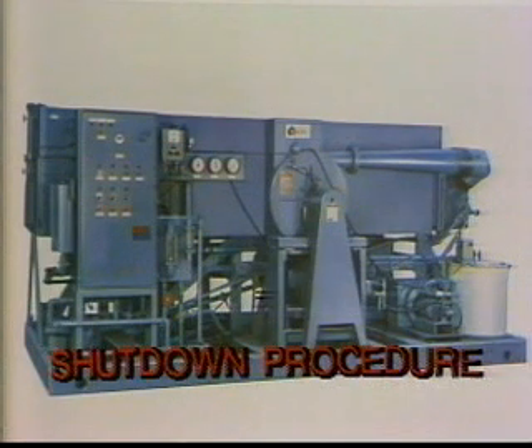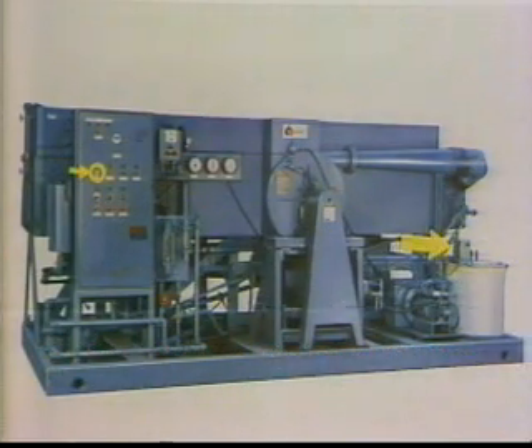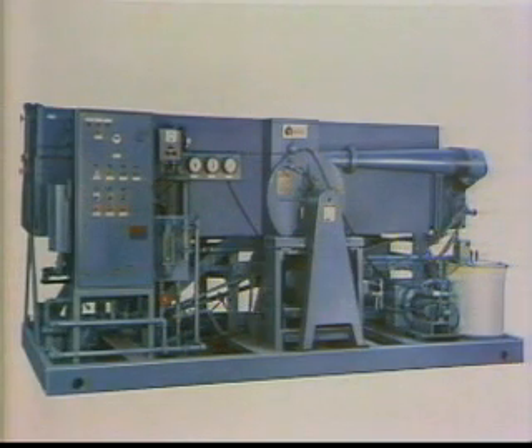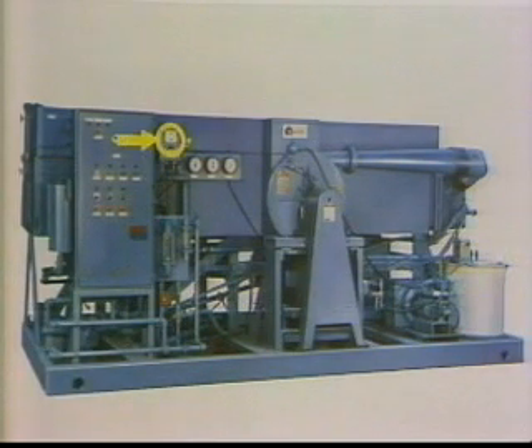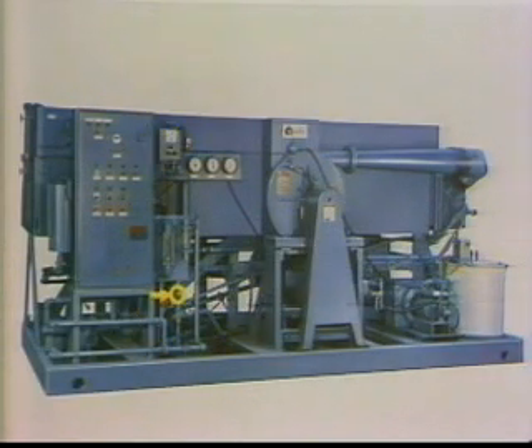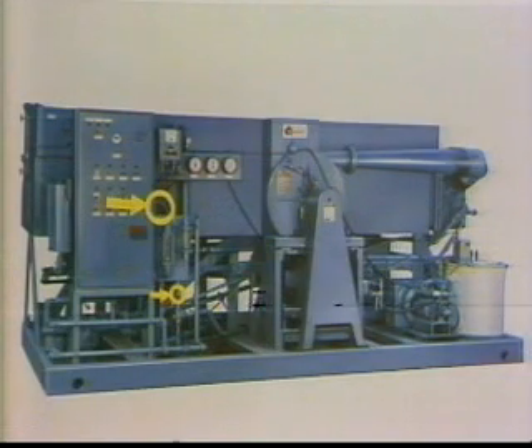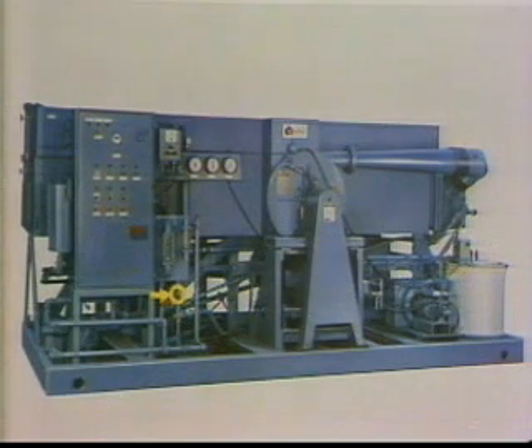Now, there are also a couple of do's and don'ts that you'll want to pay particular attention to in shutting the unit down. The feed water chemical treatment pump should be turned off at least 2 minutes before the unit is shut down. This is to flush the chemicals out so that a concentration doesn't build up in the sump and heat exchanger. Next, turn the salinity meter off and divert the distillate to waste. Throttle the distillate shutoff valve to build a distillate level in the steam chest up to about half full in the observation window. Then shut the valve off completely. This step will guarantee that enough distillate will be trapped in the unit to facilitate proper flow of makeup water to the boiler for next time.